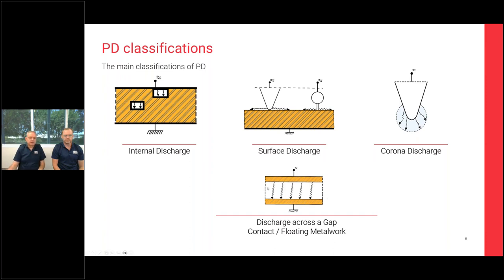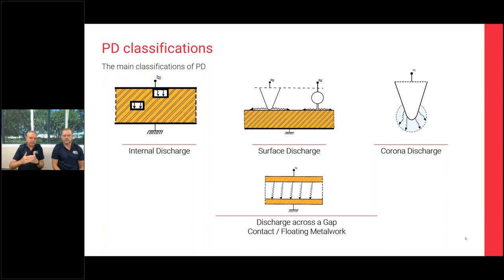When we go to a discharge across a gap, it's like a capacitor firing at the same amplitude every single time — it will build up and fire, build up and fire. This produces a very different type of pattern compared to internal discharge, which we'll see going forward.